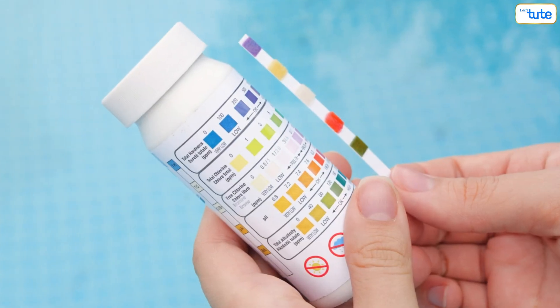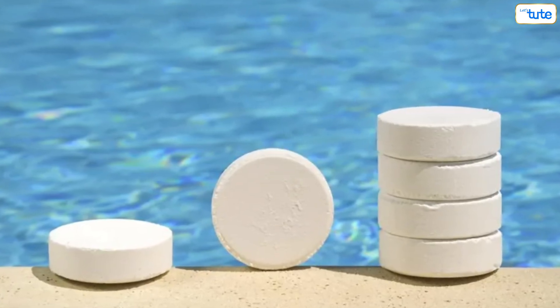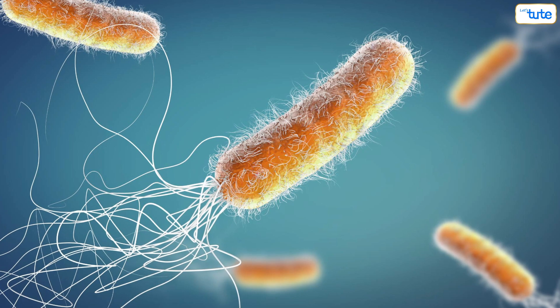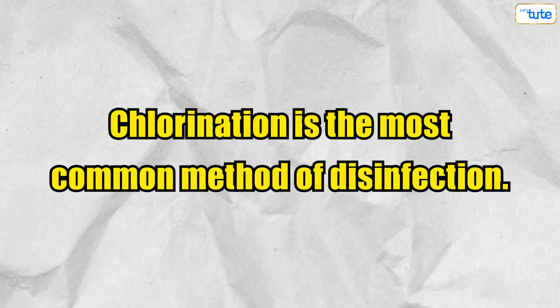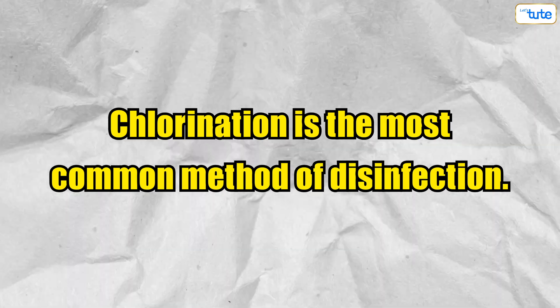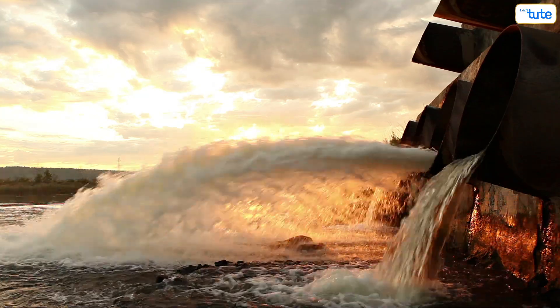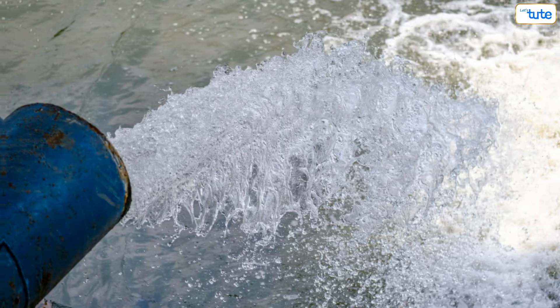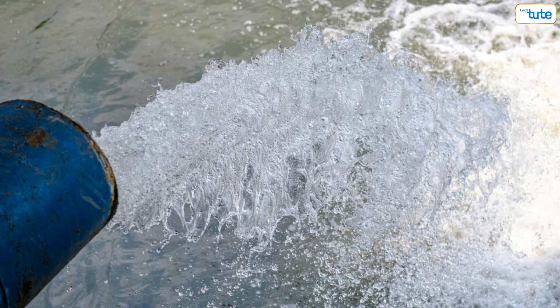The final step is disinfection. This is where chemicals like chlorine or ultraviolet light are used to kill any remaining harmful bacteria and viruses. Chlorination is the most common method of disinfection. After treatment, final testing is done to ensure the wastewater has met certain standards set by the government. These standards make sure that the water is safe to use and won't harm the environment.